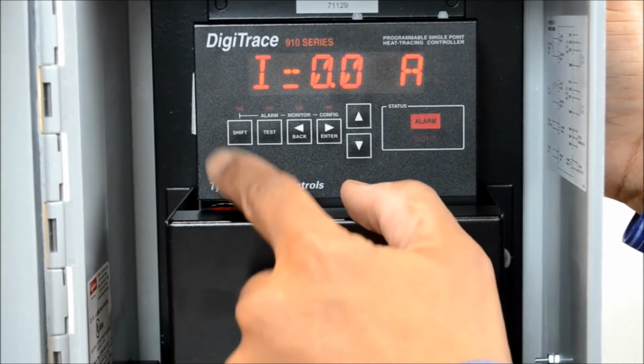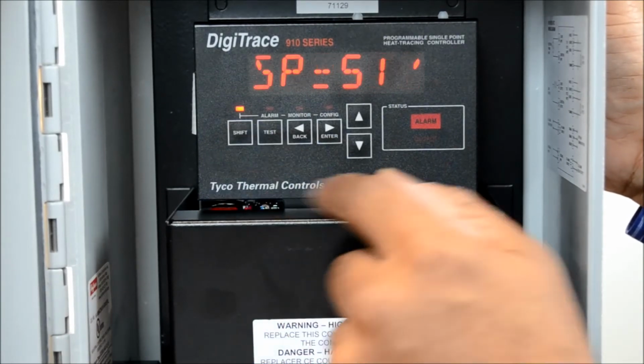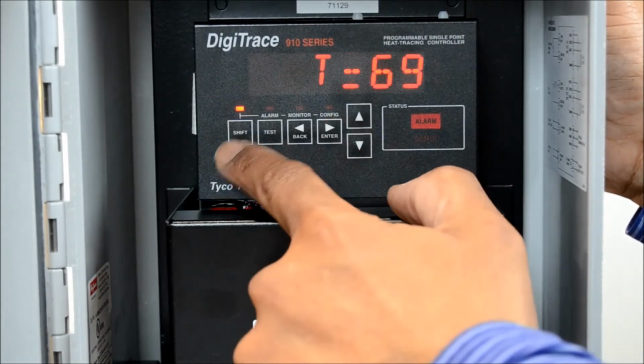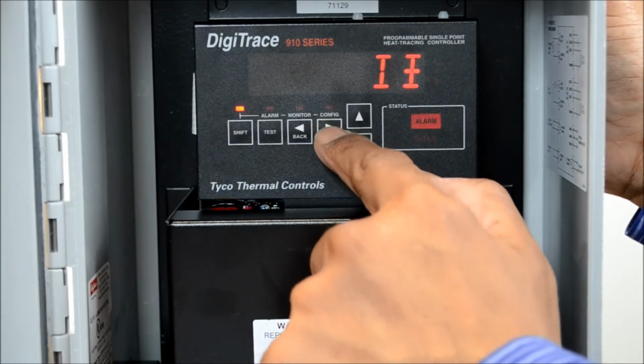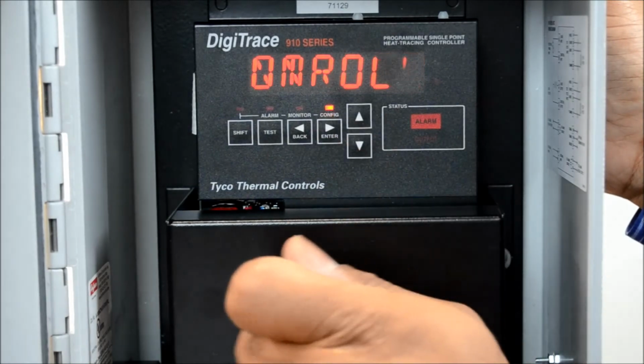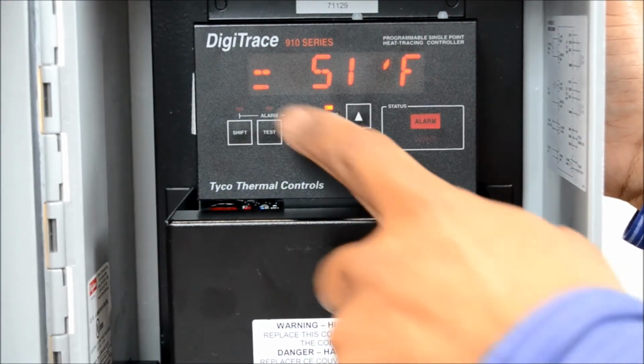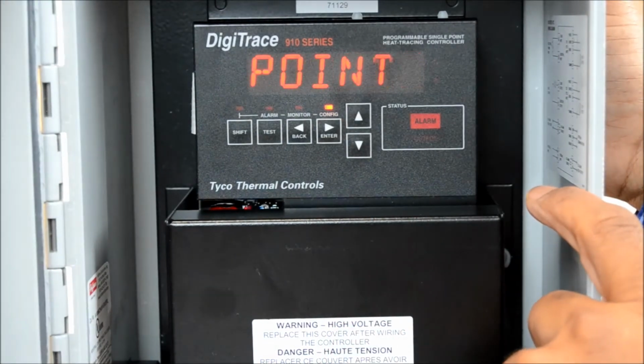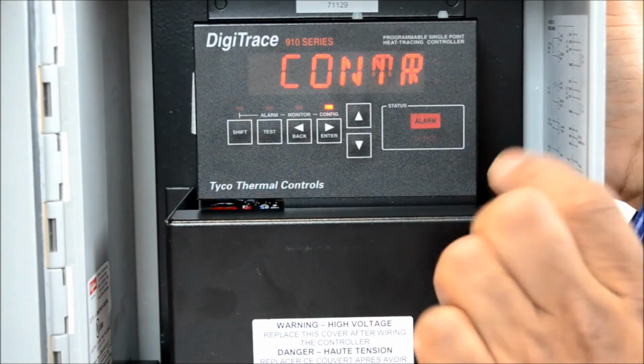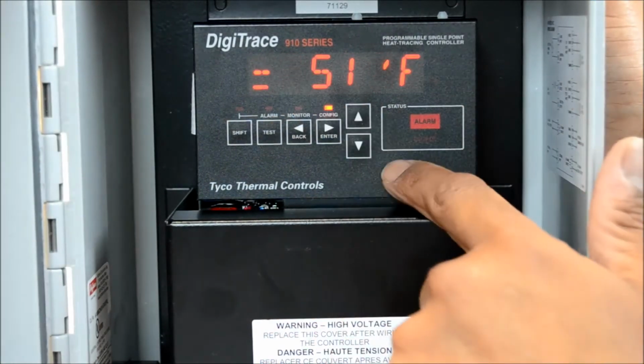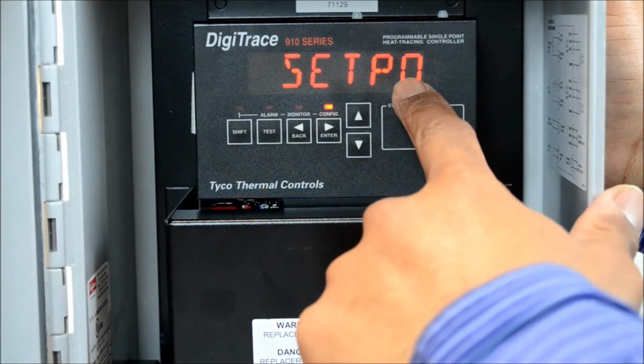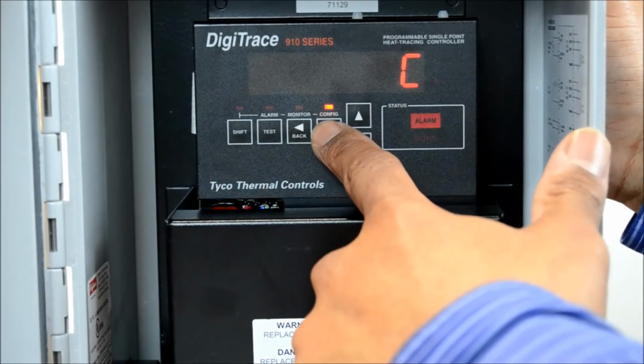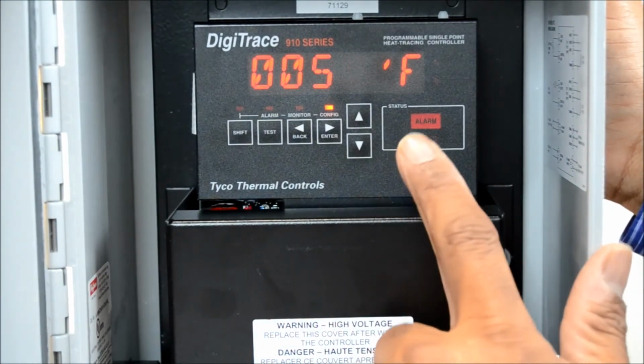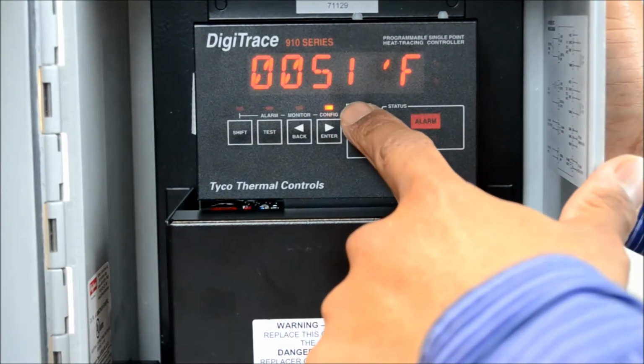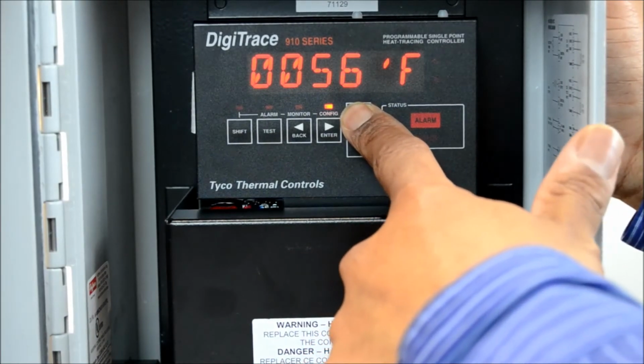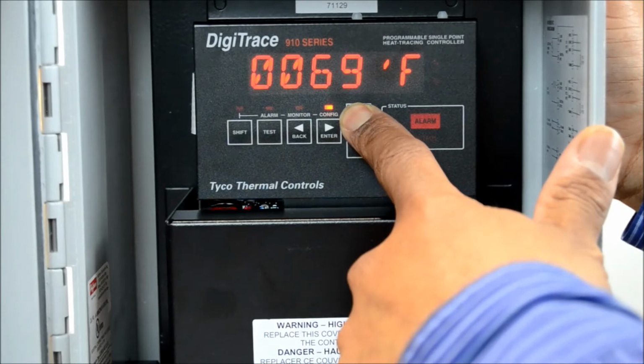But let's go into the set points and let's cut the heat trace on. You can manually cut the heat trace on by going to Shift and the Enter button, which is the configure button up top. You press that, the first menu you have is set point. Right now, the set point is set at 51 degrees, but the temperature is 60 plus degrees. So in order to cut this on manually, what I'm going to have to do is raise the set point and change it. So you do that by hitting Enter again. Now you see the blinking light, and that will allow us to change the set point. So I'm going to raise this up to, let's go to 75 degrees Fahrenheit.